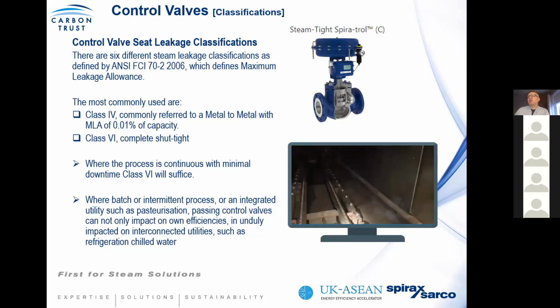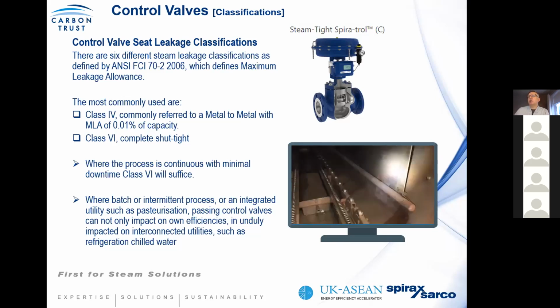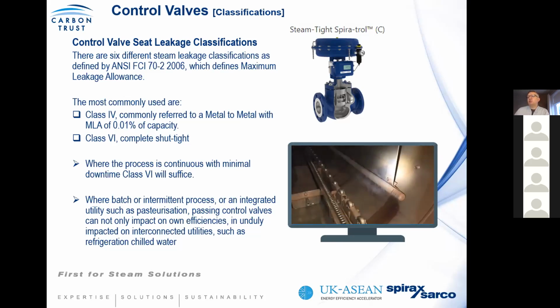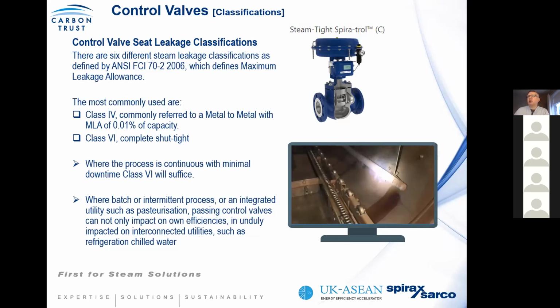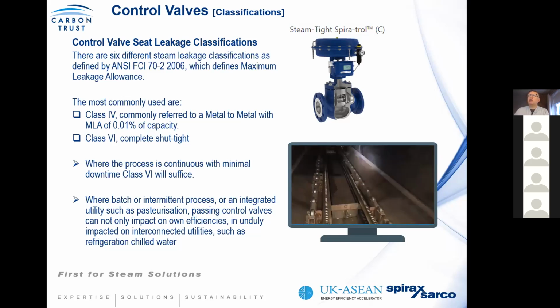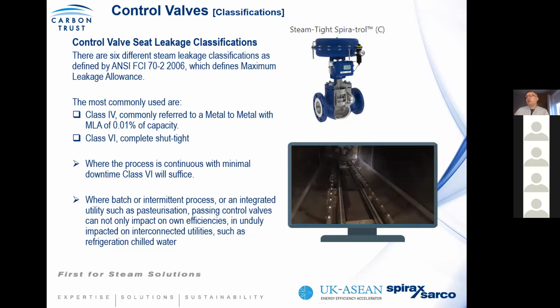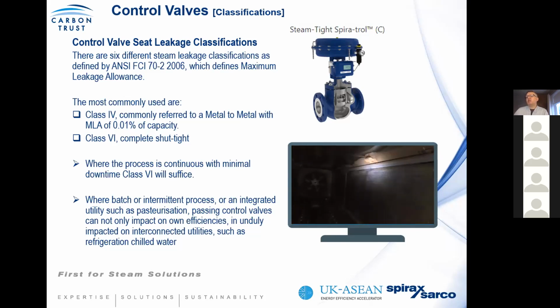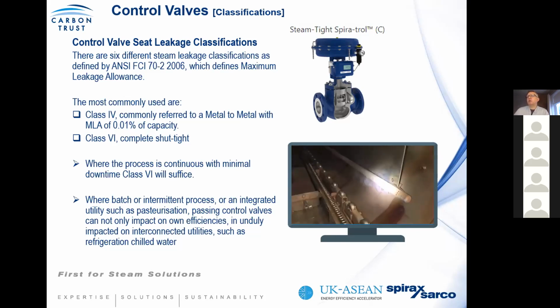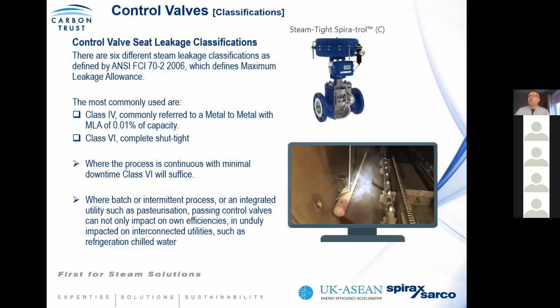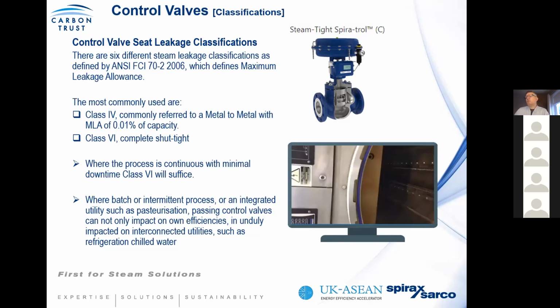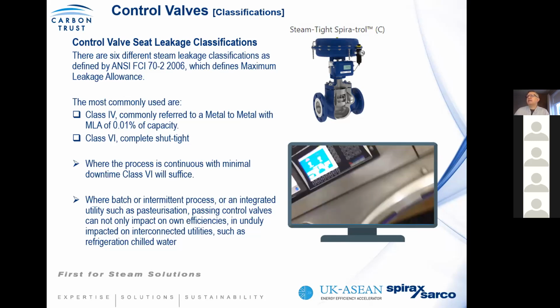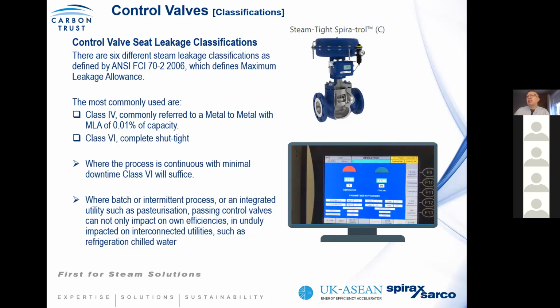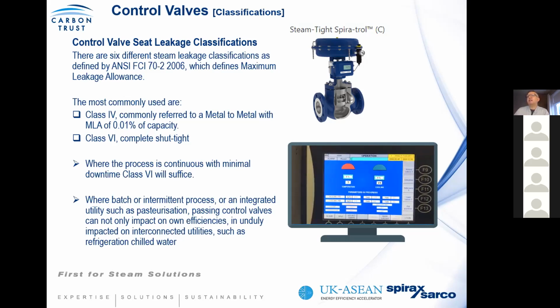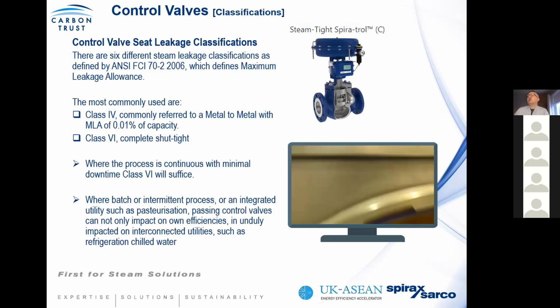In your process though, you need to consider two things. If your process is continuous, where the steam is on 24 hours a day, 7 days a week, you could argue the class 4 valve will suffice, because by virtue of the fact there's always addition of steam. However, if you have a batch or intermittent process, or where it's integrated, like in this case example for pasteurization, any leakage on the steam system translates to additional cooling when in the cooling phase.